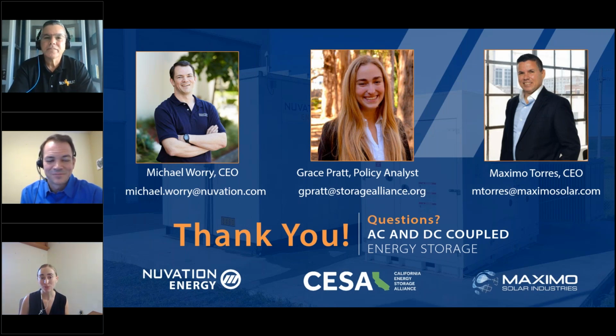For the DC coupled solution, this question is for both of you: what are the key differences at the point of interconnection, for example with protection, if any? Maximo, are there differences specific to Puerto Rico in your protection requirements? And Michael, if you know about different jurisdictions that would help. As long as you stick with the National Electric Code, you'll have protection on the DC side and protection on the AC side. In an AC coupled solution, you do need protection per AC connection, in line with the National Electric Code.